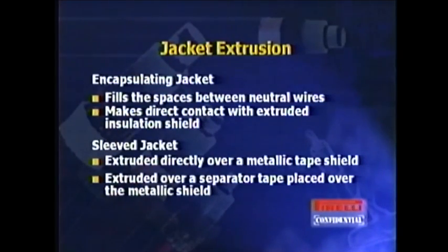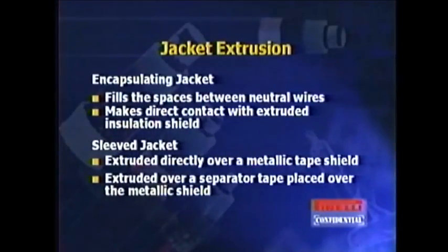There are two basic types of jackets on power cables. One is called an encapsulating jacket, and this essentially is used on concentric neutral wires, where the jacket would be extruded to fill the voids between the neutral wires. Another type of jacket would be a sleeve jacket. Taking that same scenario as a concentric neutral cable, you have some type of a separator tape, be it a water-soluble tape or maybe a mylar separator tape, and then sleeve the jacket over that so you have a smooth interface on both sides. Both have their advantages and disadvantages.